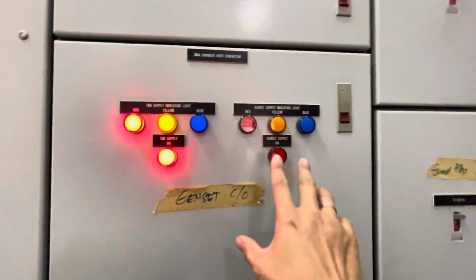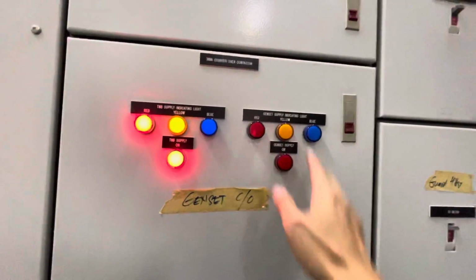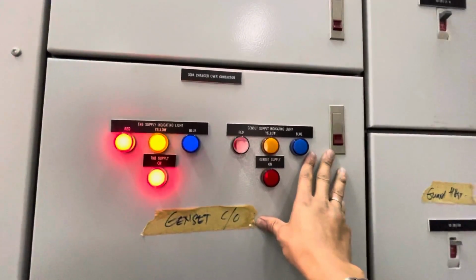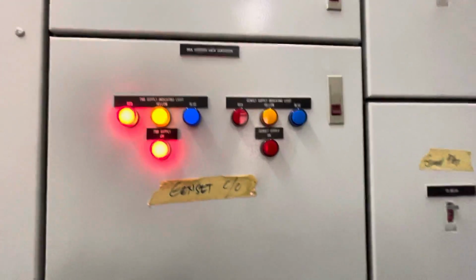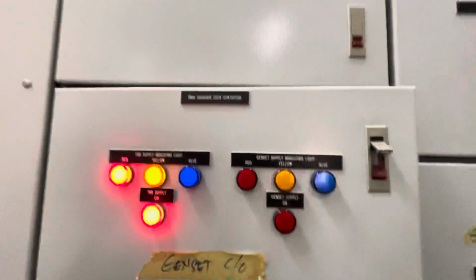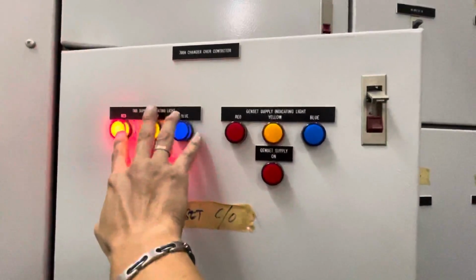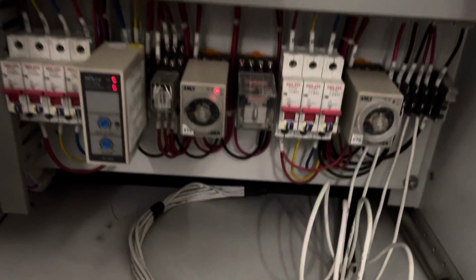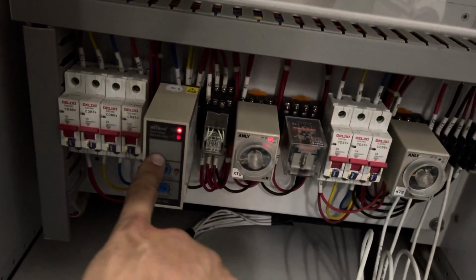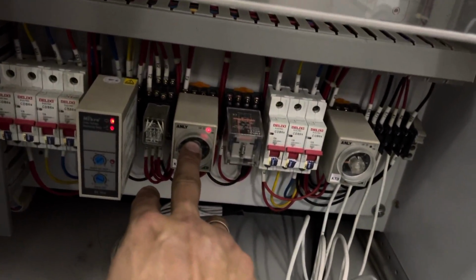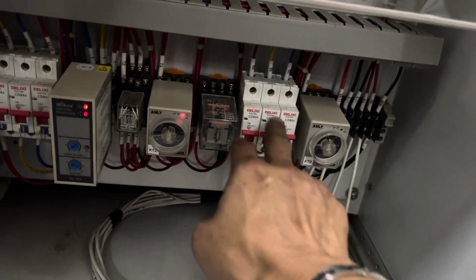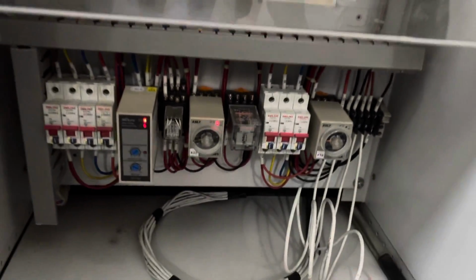So we are going to test the genset running from this ATS panel remotely without going into the genset room. Okay. So now main supply available, genset is stopped. Okay. So here we have the ATS control panel. This is the UVR relay, main supply timer, genset control MCB.